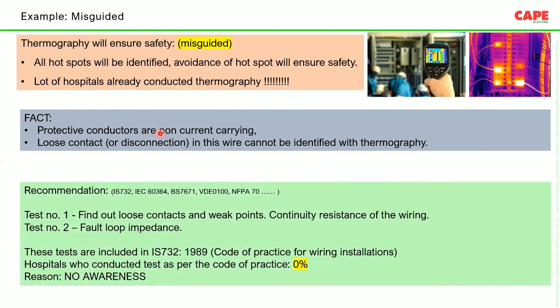Here, the problem with thermography is that loose contacts in the live conductors can be found, whereas in the earth conductor or protective conductor, you cannot find loose contacts and problems. So IS 732, and also the National Electrical Code 2023, which was launched on 6th January, have recommended two tests which can find loose contacts in wiring. Test number 1 is called continuity resistance of the wiring. You are supposed to measure the continuity resistances. And test number 2 is fault loop impedance. With these two tests, loose contacts not only in the phase or neutral conductor, but in the earth conductor also can be found.